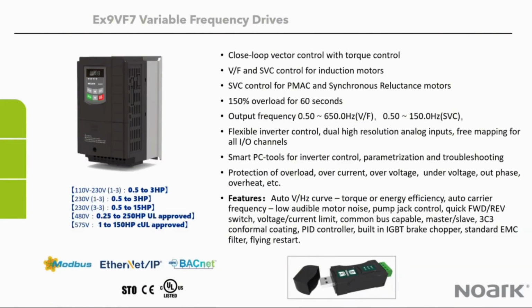And here we highlight in point form some of the various control features that we've discussed, including smart PC tools for inverter control and troubleshooting, but also our sizing. So 110 to 230 volts, single phase in, 3-phase out, 0.5 horsepower to 3 horsepower, 230 single phase in to 3-phase out, 0.5 horsepower to 3 again. And then your 230, 3-phase in, 3-phase out, 0.5 horse to 15 horse, 480 volt, 1/4 horse to 250, and 575 or 600 volt, however you wish to refer to it, 1 to 150 horsepower.